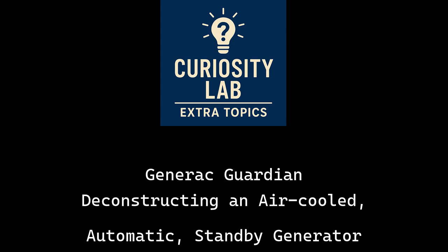A mechanical lug is way more reliable. And the 10 to number 14 rating, that's a huge range. That's massive versatility. It means that one lug can accept a giant 10-gauge main feeder wire or a standard 14-gauge wire. And the ALCU means it's rated for both aluminum and copper wire. Which gives the electrician flexibility depending on local code and material costs.